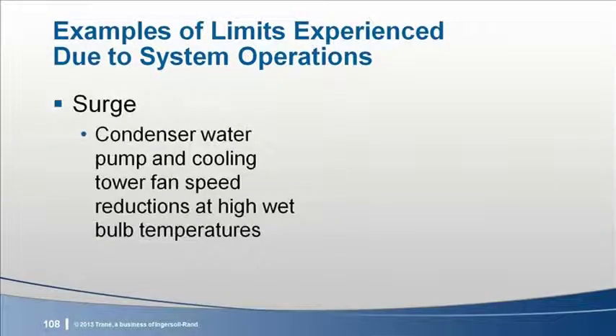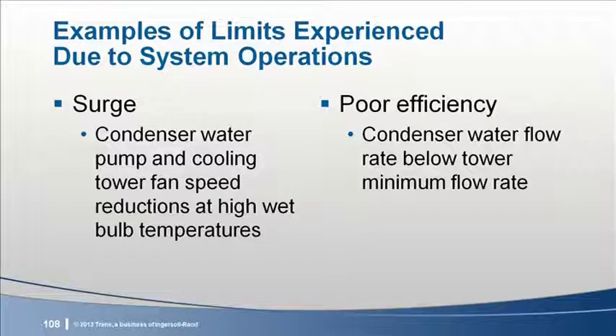During humid conditions, at reduced load, if the condenser water pump and cooling tower fan speeds are reduced too quickly, it's easy to send a chiller into surge. Another limit is experienced if the tower flow rate drops too far and heat exchanger effectiveness drops. If this occurs, the condenser water temperature and the chiller condenser pressure rise significantly. This can cause an increase in system energy usage.